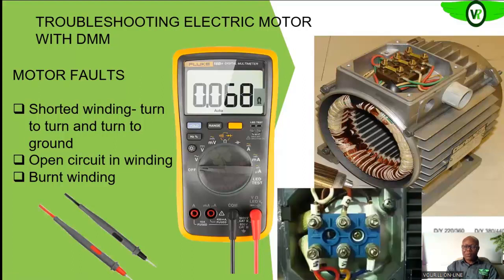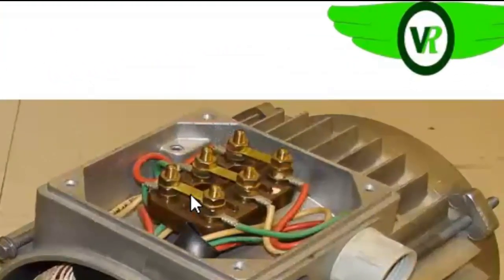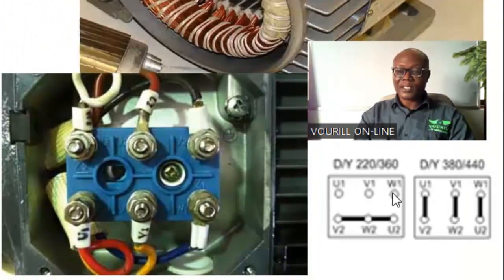So what you need to do first, remember it's a dead test, is to disconnect the shunting bars on this electric motor. Remember that all electric motors, like we said earlier, have three phase windings in them, and that is what we are seeing here. We have the U phase, the V phase, and the W phase. In rewinding, you have to start from somewhere. So the start of that winding is what is labeled 1, and the finish of the winding is what is labeled 2. When you look at the terminal block, you see that you have U1, U2, V1, V2, W1, and W2. All the ones are the start of each of the windings, and all the twos are the finish of each of the windings.